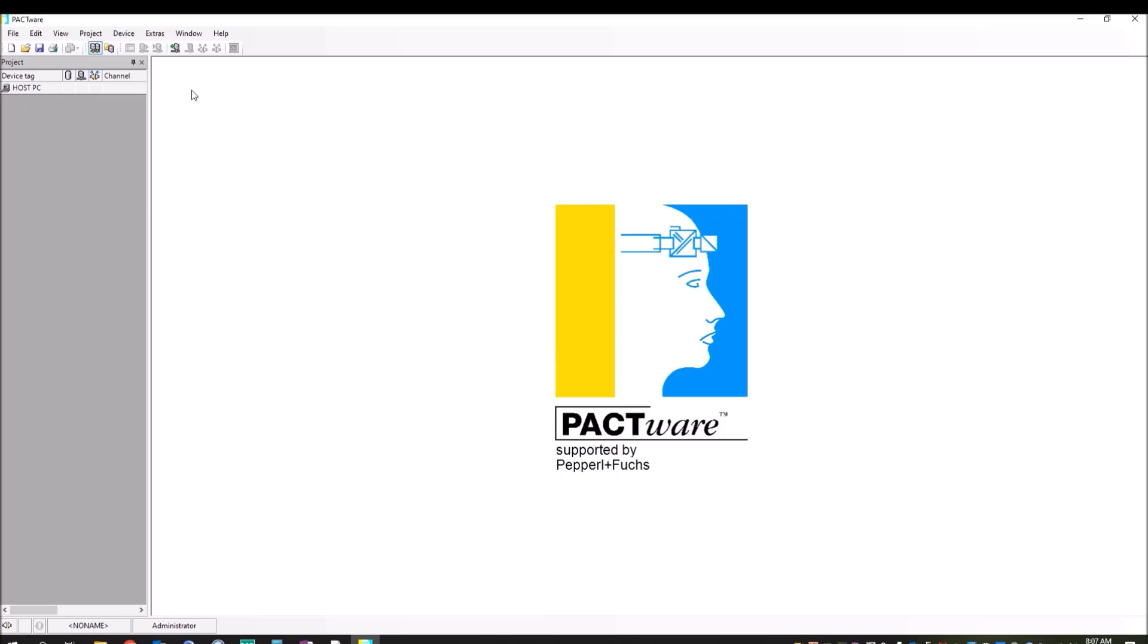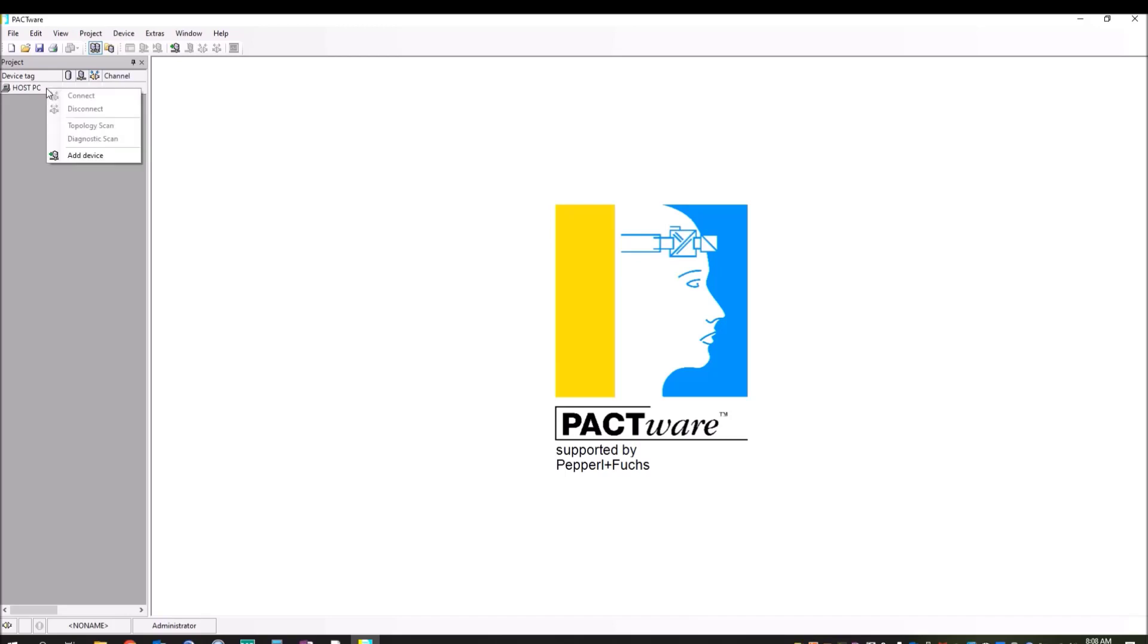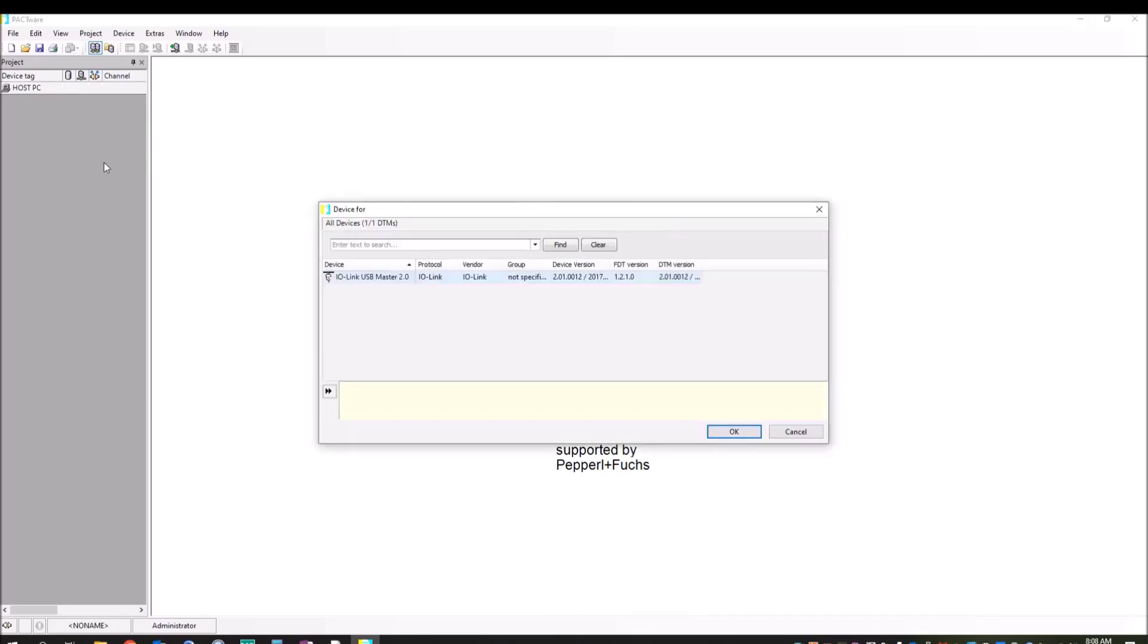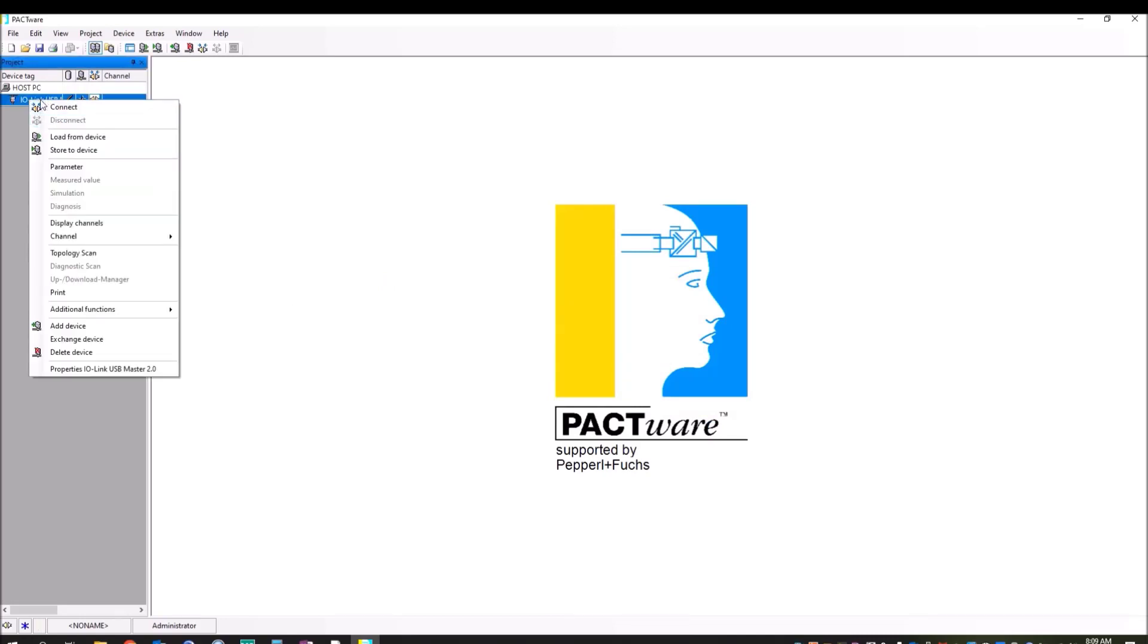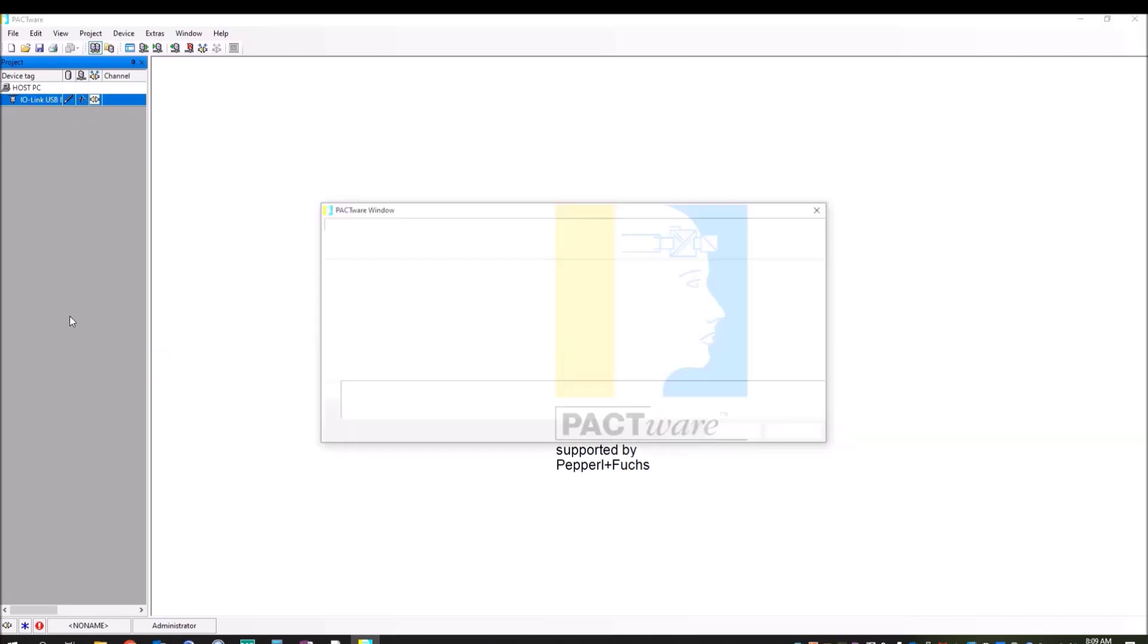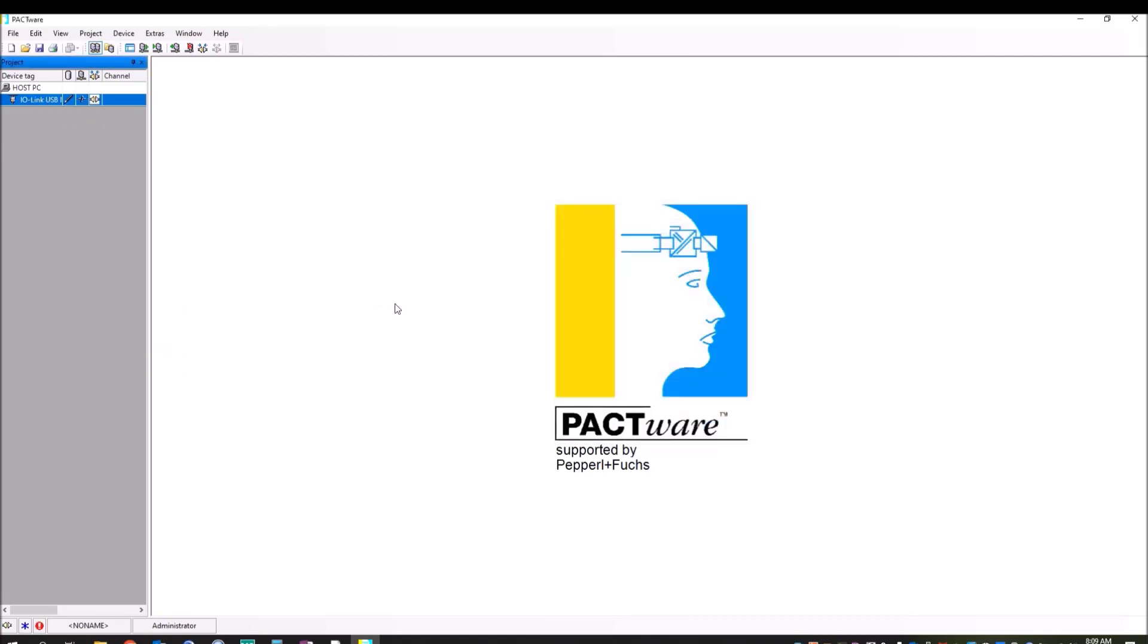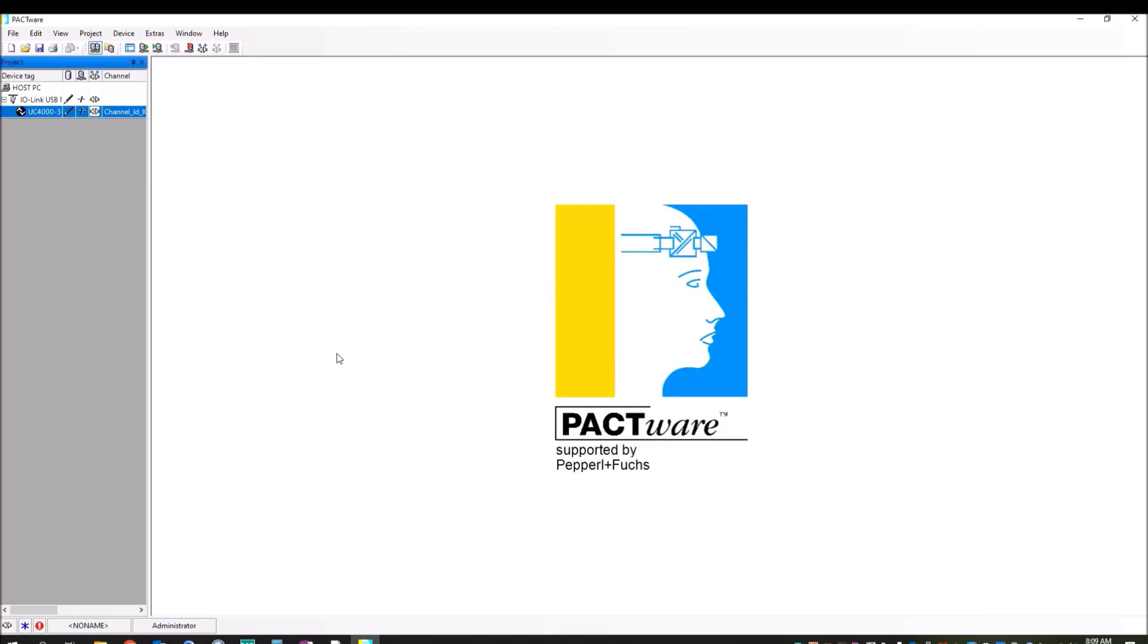Now, since we've installed the DTM for the UC 4000, the program automatically installed the USB master. So let's go in here and build a tree. When you do that, you go under the project tab. And you can see that right now we're in the host PC. The structure for this project tab is to build your way down to the device that you have. So first, we need to add the USB master, because we have to go through that to get to PACTware. So we're going to install that. Okay, now that we have the USB master added to the tree, we need to add the UC 4000 beneath that. So we will click on the UC 4000 and add that device.